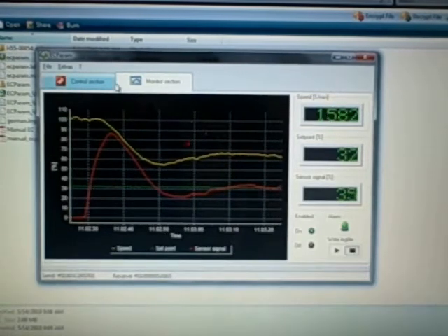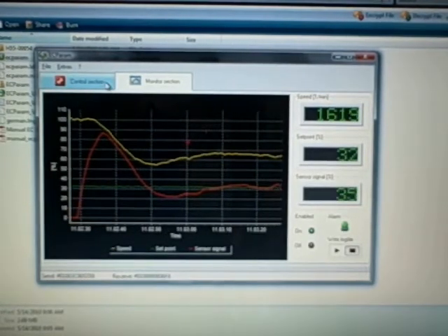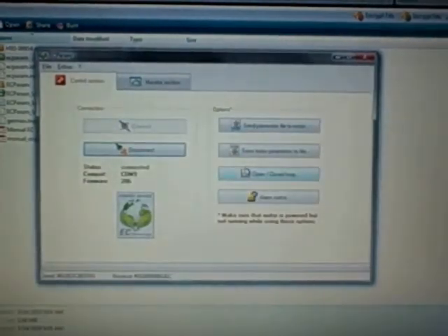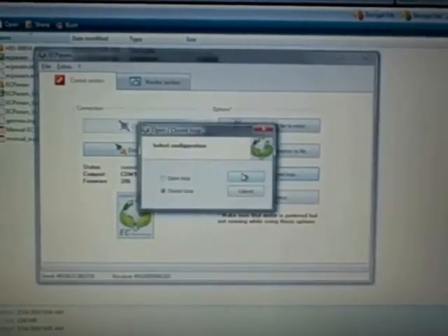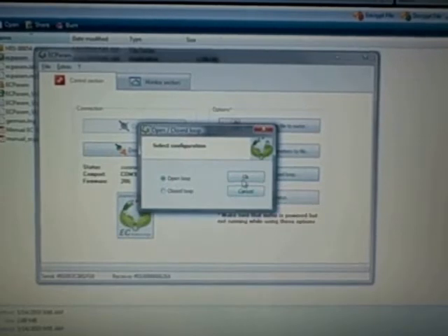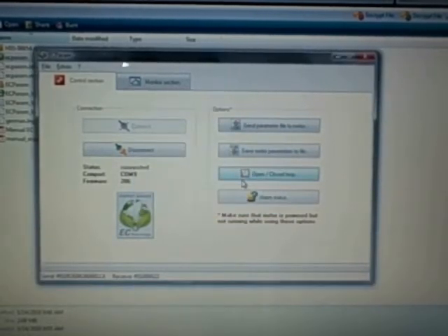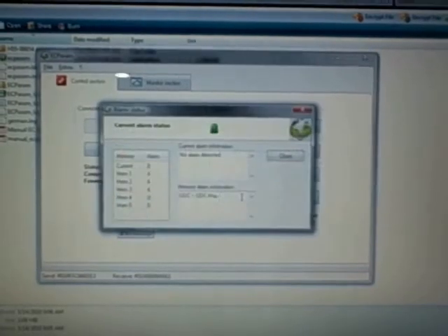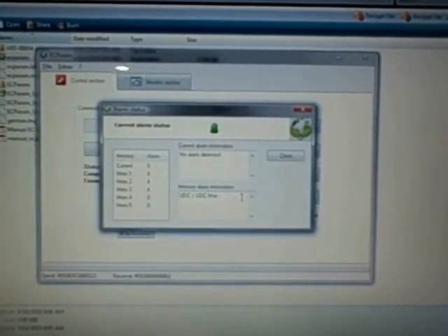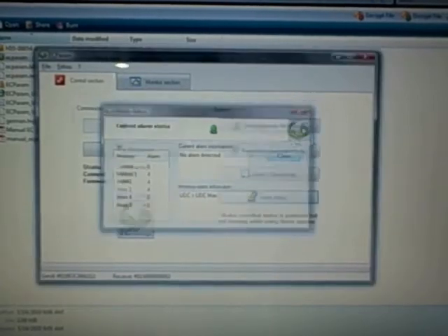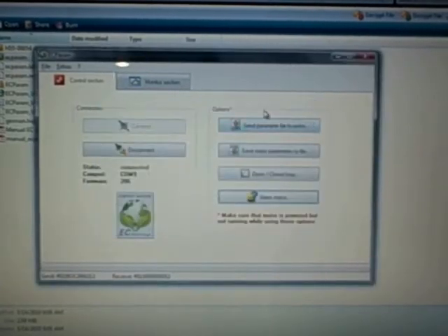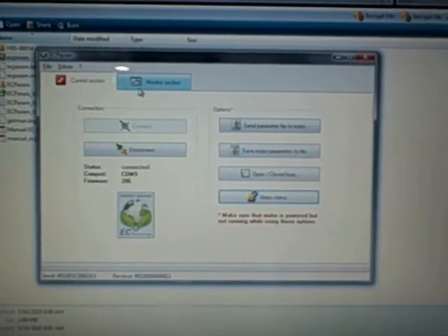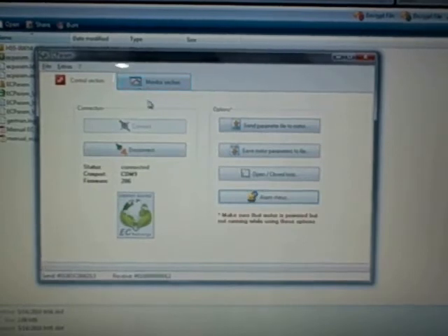Now you can close this program even with a closed loop and it will stay in closed loop. If you want it to go back into open loop, you have to tell it to go back into open loop controls. Again, the fan will stop, reset, and then start back up. You'll see any alarms. It'll show you anything whether it has an internal failure, a high temperature alarm, anything that would cause the motor to fail. Whether it be a power loss, it'll tell you there of any kind of failures.